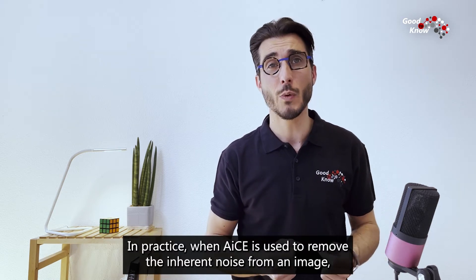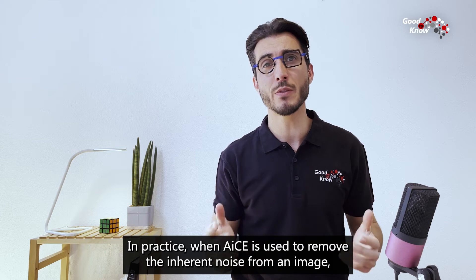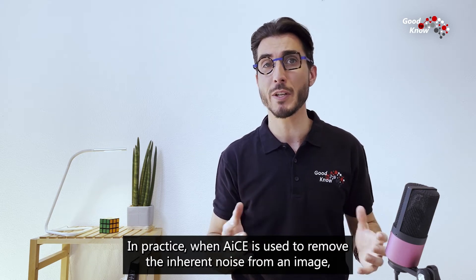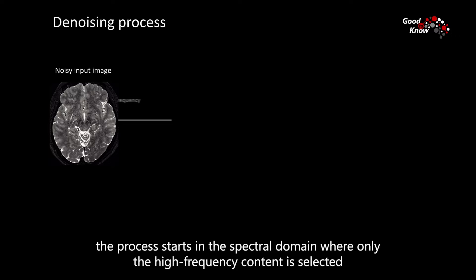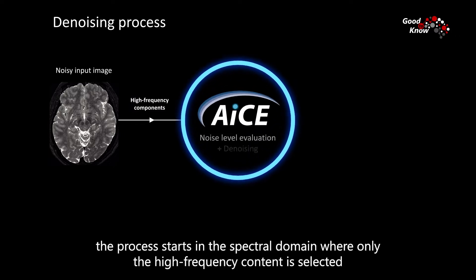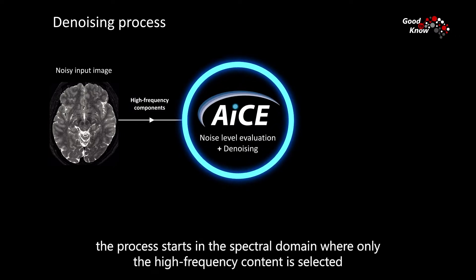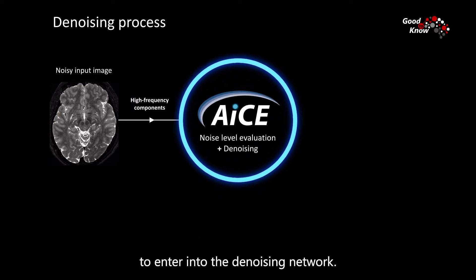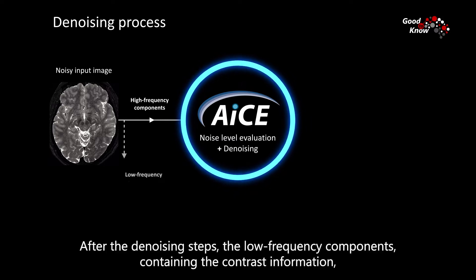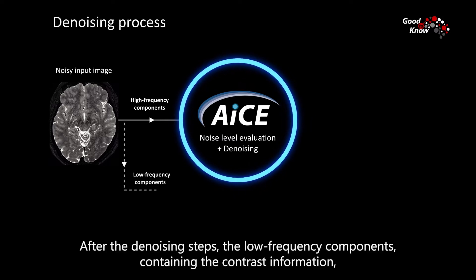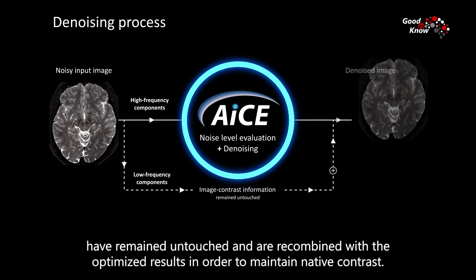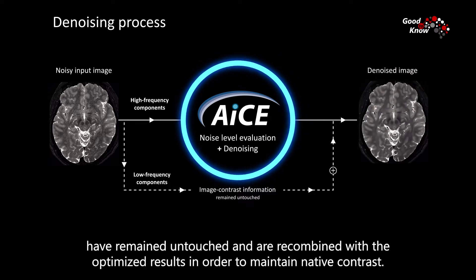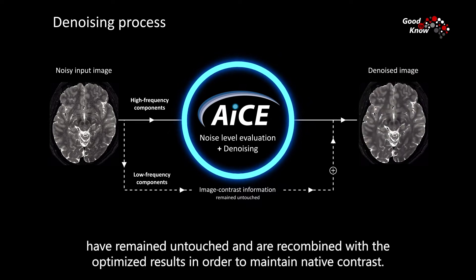In practice, when AICE is used to remove the inherent noise from an image, the process starts in the spectral domain where only the high-frequency content is selected to enter into the denoising network. After the denoising steps, the low-frequency components containing the contrast information have remained intact and are recombined with the optimized results in order to maintain native contrast.